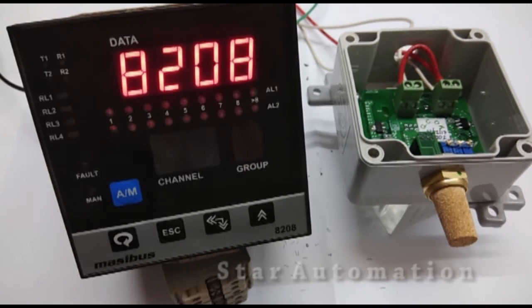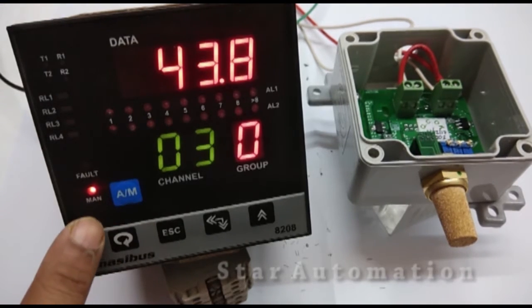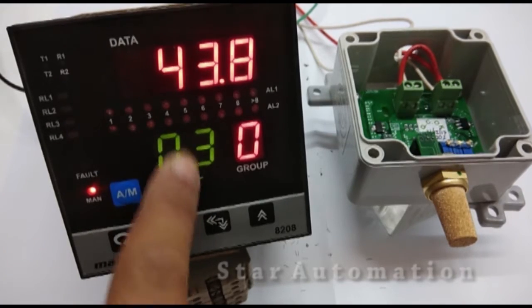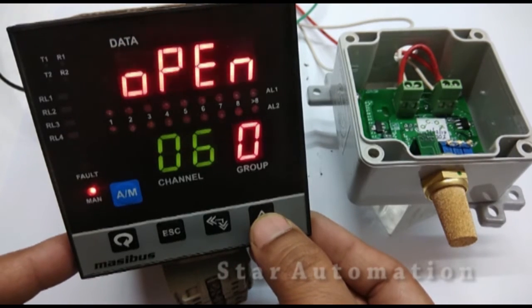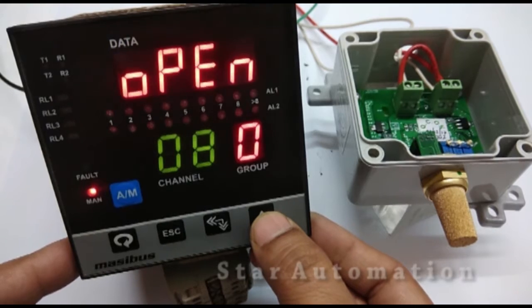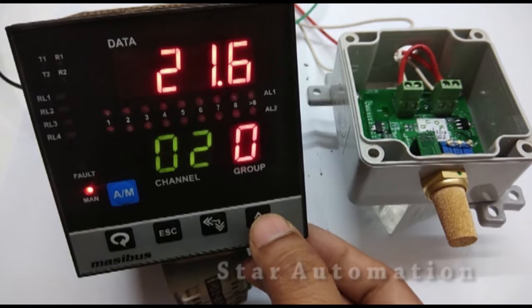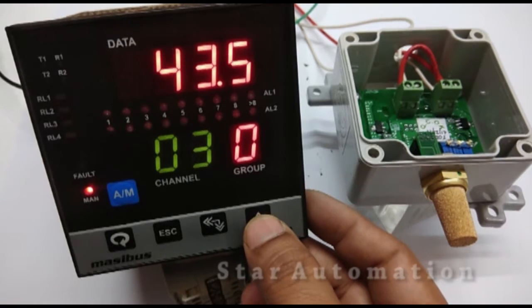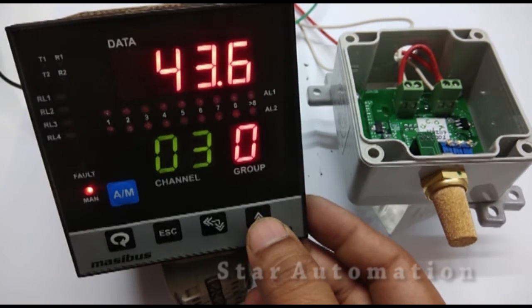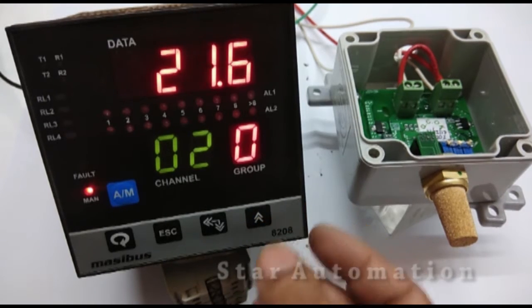Now we will switch on and power up the system. At the upper channel we are getting the temperature value. Channel 3 is showing 43.8. Channels 6, 7, and 8 show open circuit as there are no connections there. At channel 2 we are getting 21.6 degrees, which is the air temperature, and at channel 3 we are getting humidity at 43.5%.